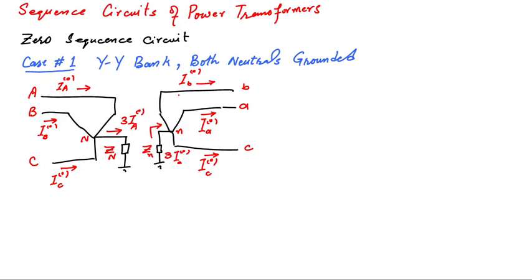And if the zero sequence current is flowing into the low voltage side, the direction of current will be from neutral to ground on the low voltage side, and from ground to neutral on the high voltage side, and the direction of all these zero sequence currents gets reversed, being out of the transformer. When the transformer is part of an interconnected power system, current can flow in either direction, from high to low or low to high side.